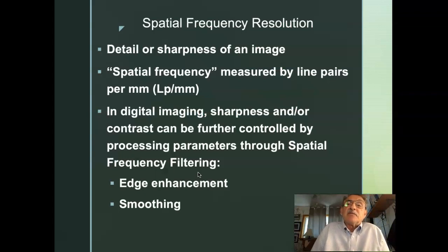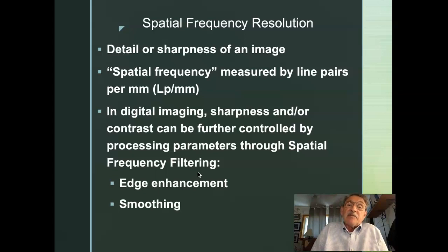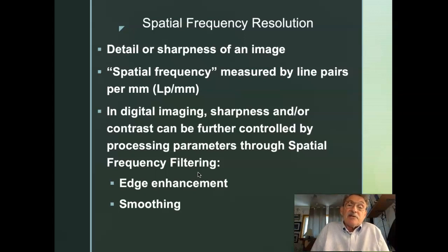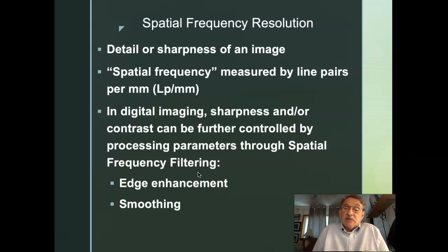Spatial frequency and spatial resolution refer to the detail or sharpness of the image — the focus, clarity, and ability to see fine details. Spatial frequency is measured in line pairs per millimeter. The more line pairs per millimeter we can see, the better the spatial resolution. In digital imaging, sharpness and contrast can be further controlled through spatial frequency filtering, including edge enhancement and smoothing — post-processing functions that may or may not be applied.